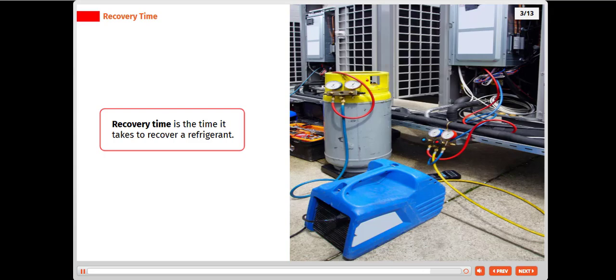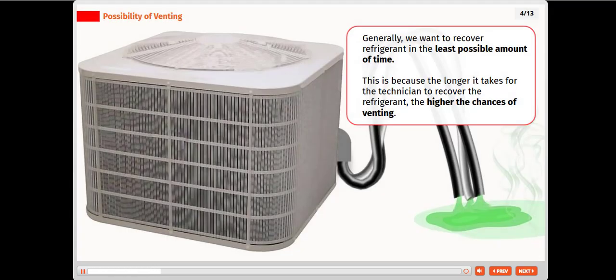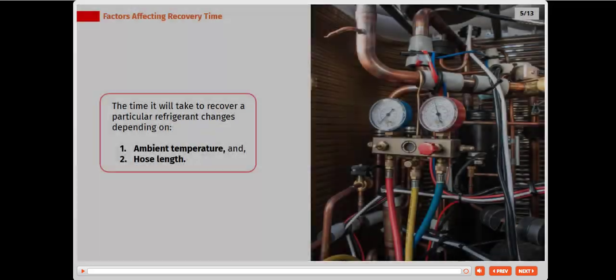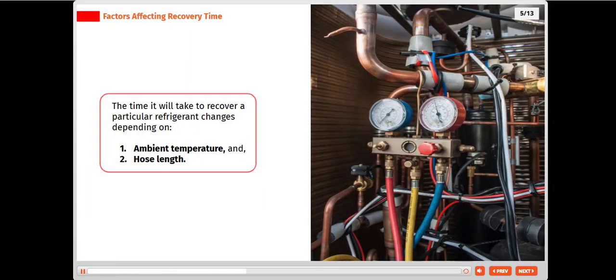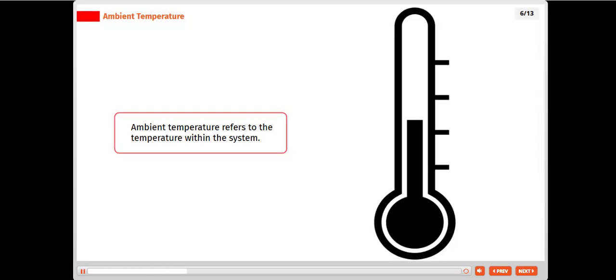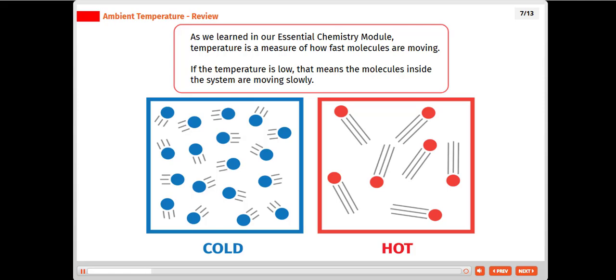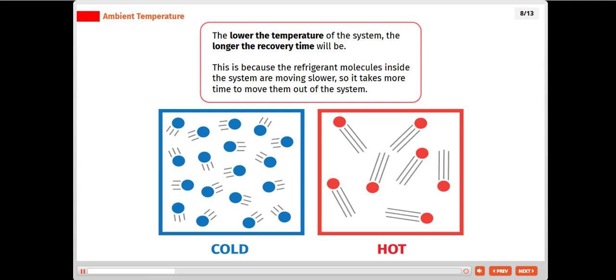Generally, we want to recover refrigerant in the least possible amount of time. This is because the longer it takes for the technician to recover the refrigerant, the higher the chances of venting. The time it will take to recover a particular refrigerant changes depending on ambient temperature and hose length. Ambient temperature refers to the temperature within the system. As we learned in our essential chemistry module, temperature is a measure of how fast molecules are moving. If the temperature is low, that means the molecules inside the system are moving slowly. The lower the temperature of the system, the longer the recovery time will be. This is because the refrigerant molecules inside the system are moving slower, so it takes more time to move them out of the system.